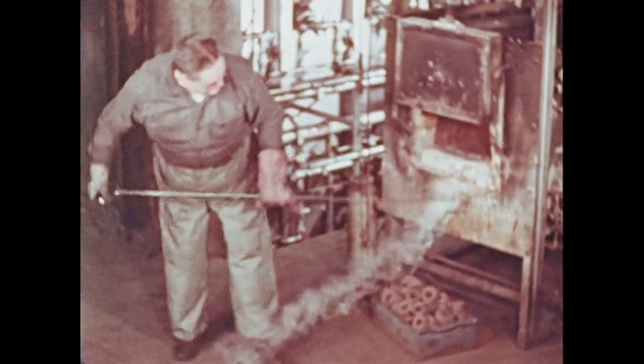You cannot rely for safety on the fact that a liquid has a high flash point. Some of our worst fires have been in heat treating areas, where large quench tanks contain hundreds of gallons of oil. Quench oil does not ignite readily unless it is first heated to its flash point. What often happens is that a conveyor gets hung up, a red-hot part remains partly immersed, and the oil heats up — soon it catches fire. Eventually, as all the oil becomes heated, the fire can become just as intense as if the liquid were gasoline or any other low flash liquid. So wherever high flash liquids are heated or might accidentally become heated, treat them with the same care as the more easily ignited liquids.